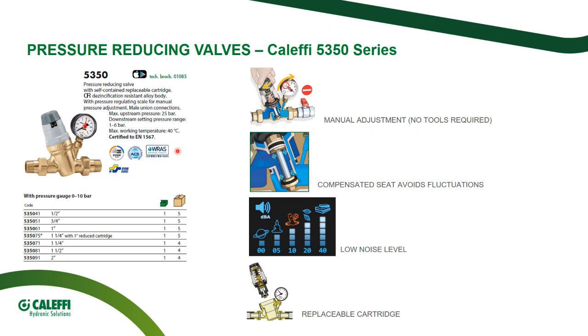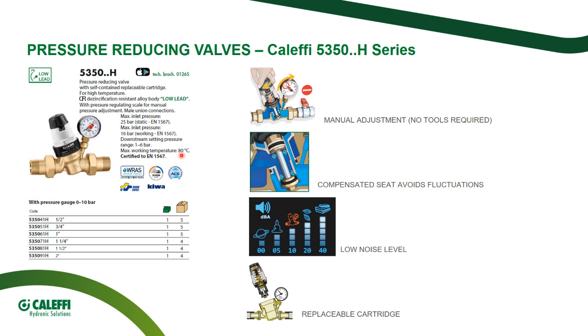And of course, the pressure reducing valve has to be certified according to the most recognized international standards for potable water application. So this has to be valid for both cold water devices, which we identified up to 40 Celsius degrees, but also for hot water devices up to 80 Celsius degrees. The devices are very similar, the shape is similar, the operation is the same, but they are not the same valve. Especially hot water operating conditions are very stressful for the devices. So we had to change some technical details and some materials in order to comply.